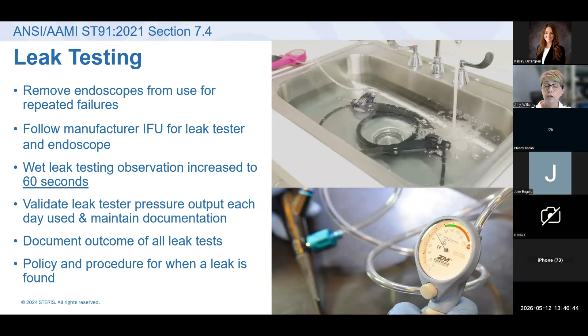Wet leak testing. Observation time has been increased to 60 seconds. It used to be 30. We now know that for a wet leak test, 30 seconds is not enough. So they bumped up the time frame and now it's a full minute. So part of your quality process is making sure that people are actually observing for a minute, okay? And all of that obviously should be written in policy, and that your staff are trained on that and that they know what to do when there is a leak. What do you do with that device? Part of your policy should specify how many times are we going to leak test the device before we take it out. We're going to do it once and pull it if it fails. Are we going to do it once, repeat it if it fails, and then pull it? All of that should be specified.